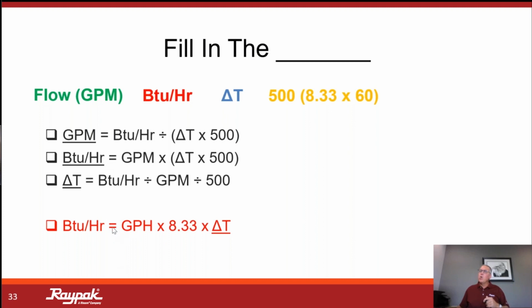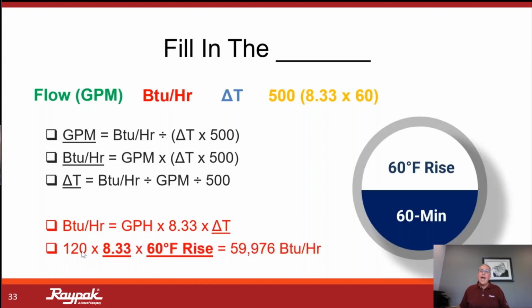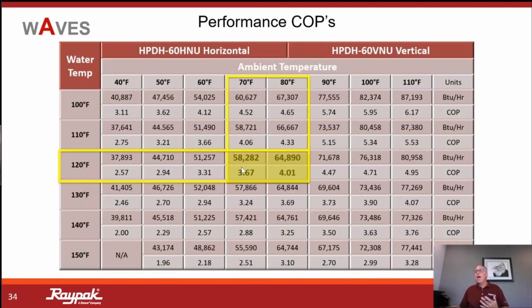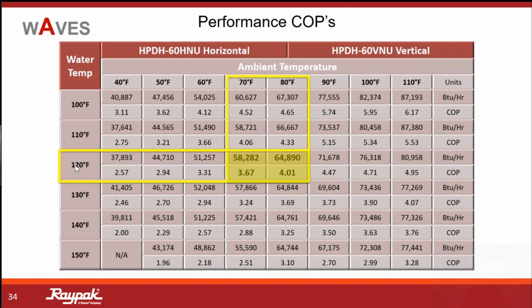So here's where I think this becomes important. We can take the value of time off of here as it pertains to GPM and just do gallons per hour, right? So we know that we had 120 gallons heated in that scenario in the lab, that 120 gallon tank. Here's the weight of a gallon of water. We knew we were getting about a 1 degree rise per minute, so a 60 degree rise an hour. That roughly gives us 59,000, just under 60,000 BTUs. And for me, I go back and say, let's extrapolate that and go back and say, where am I at? Interpolate, really. So with 120 degree water temperature and those 59,000 BTUs, I knew my COP, my efficiencies, were somewhere in this realm, pretty healthy. You see how that works a little bit?